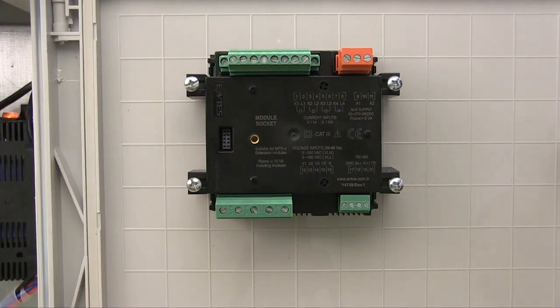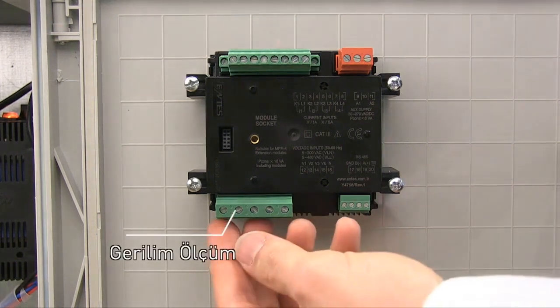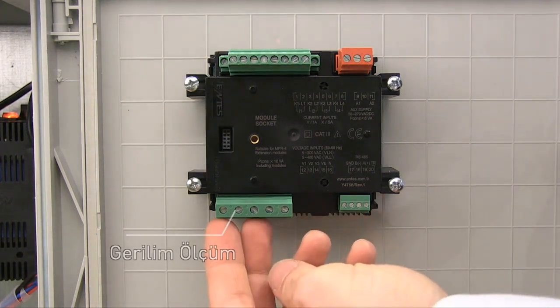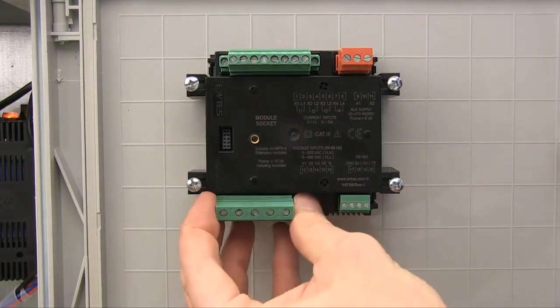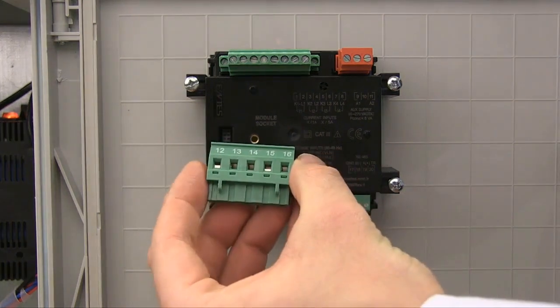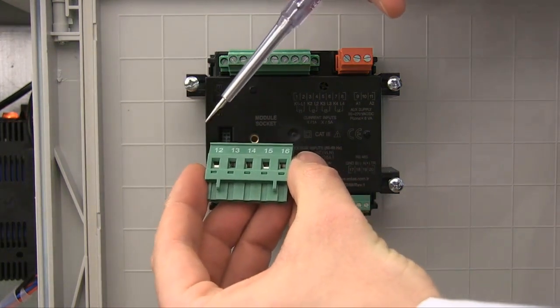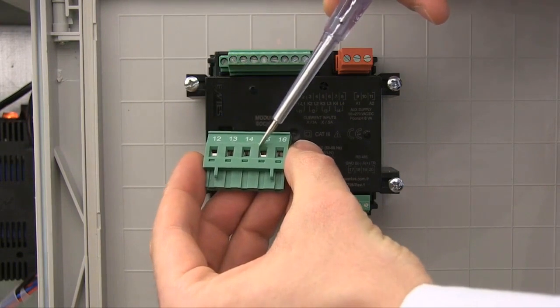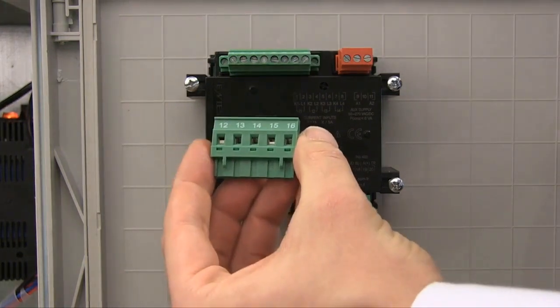The order of connections in the cabling is up to your preference. Here, we are first making the voltage measurement connections. The voltage cables mounted on the bars should be connected to the voltage measurement terminal located at the bottom left of the device. The first 3 terminal inputs are for measuring the voltages of the 3 phases.